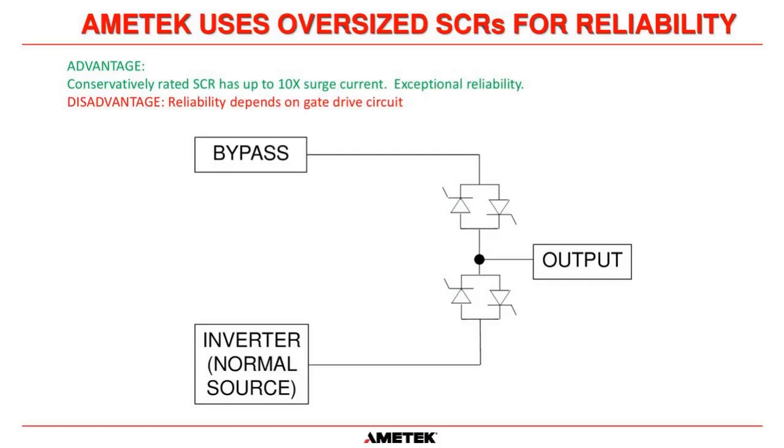The only question is now what you use as a gating circuit. Somehow, if you recall, I said, always get to the bypass source if it's available. Well, if our control circuits fail and our power supplies fail, we can't use that as an excuse of why we can't get to the bypass. So we're going to find a way. We have to be able to make sure we can always gate on the bypass source. If we have all kinds of failures, get to the bypass, and that includes power supplies and things like that. So we'll see how that happens here.